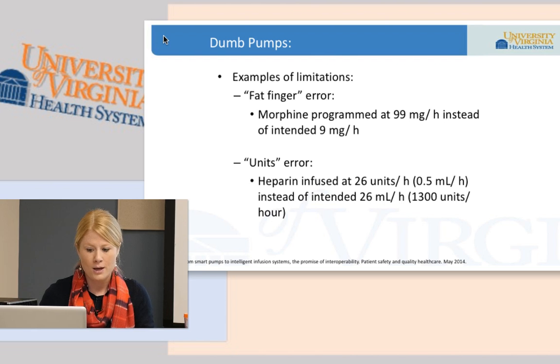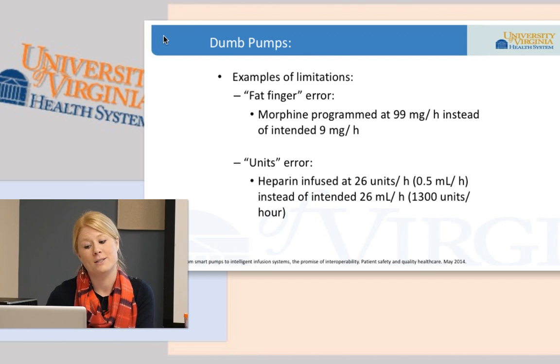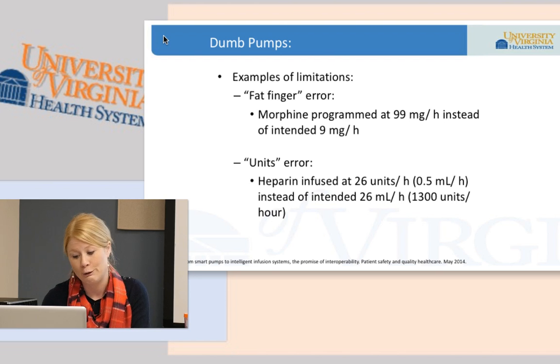Some of the errors that were arising with these dumb pumps included the fat finger error. Like it suggests, you would push more than one button than you were meaning to push. We'll see a picture in a minute, but the pump itself made it pretty easy to push more than one button on some of these pumps. An example of this would be morphine being programmed at 99 milligrams per hour instead of the intended 9 milligrams per hour, which, as we can see, would be a huge problem for the patient and a huge error.